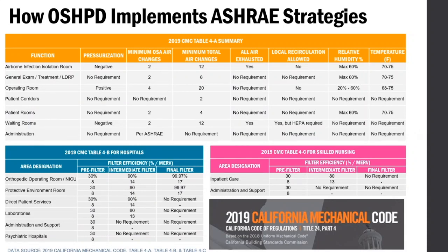Sure. Basically this table is a summary of the 2019 California Mechanical Code for filtration efficiencies, air change rates in different types of healthcare applications, required pressurizations for different categories of rooms, whether air needs to be exhausted from the space 100%, and temperature and relative humidity requirements. So all of those 9 categories are generally covered in these 3 tables in the code.